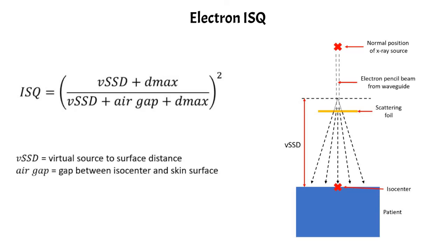And it is by no means a perfect model of dose falloff. And in fact, at really extended SSDs, the further we get away from that 100 centimeter condition, we actually might just go ahead and measure the electron output factor rather than using an inverse square correction, because it's a little bit more accurate to just measure it at those extended SSDs.